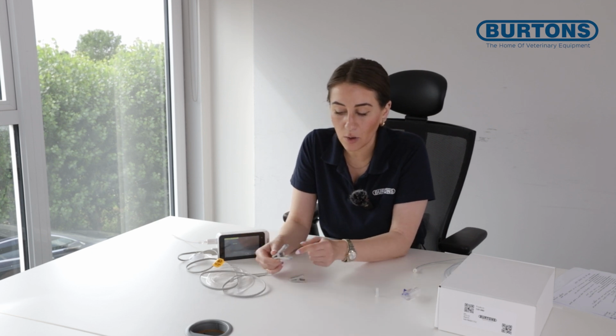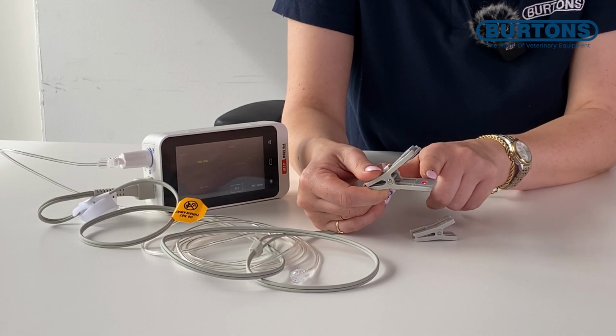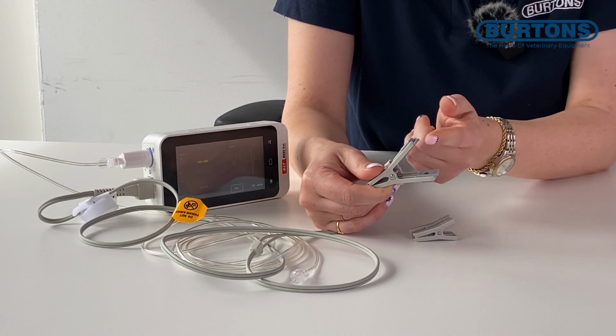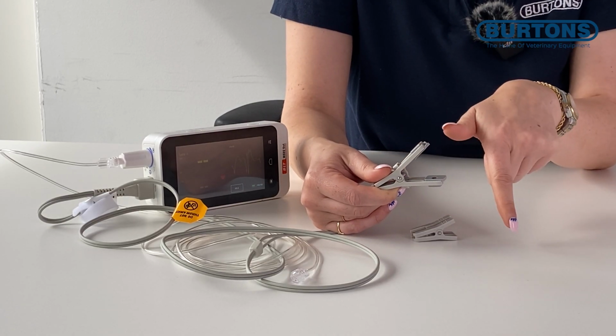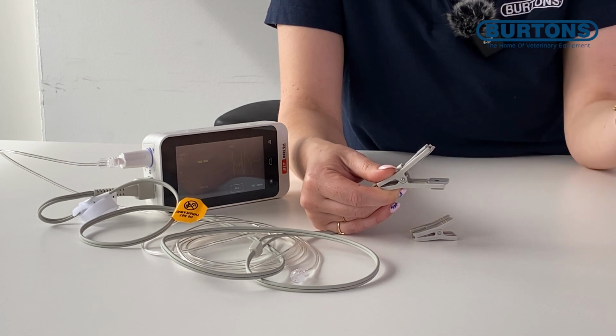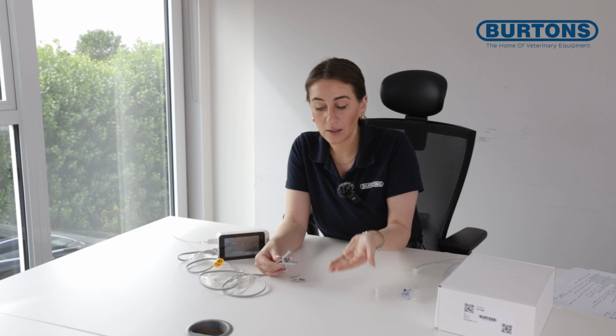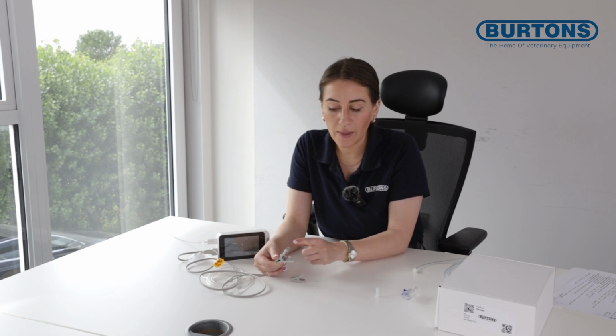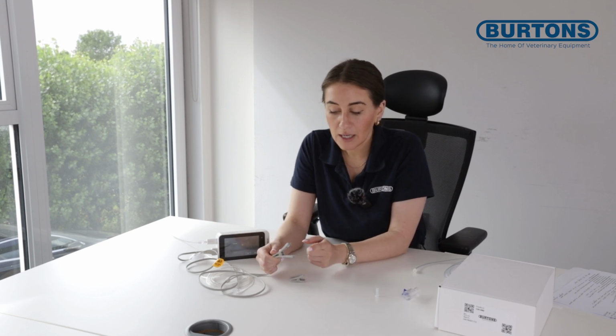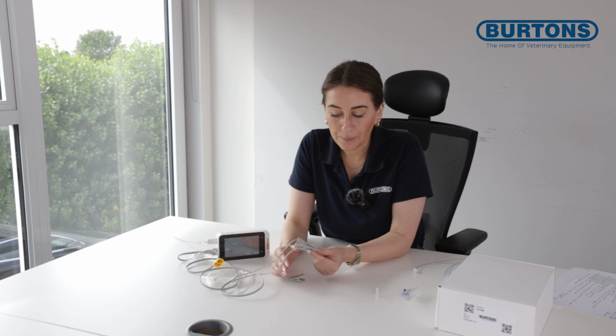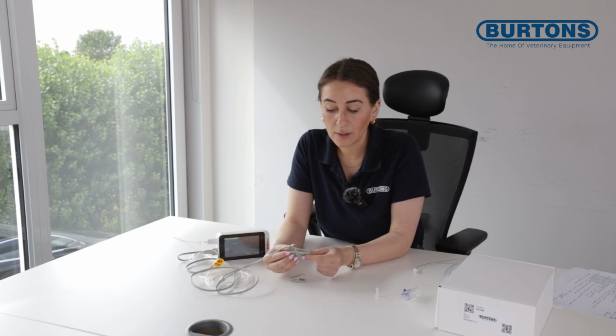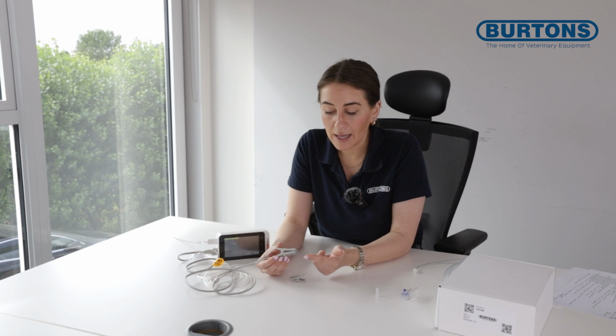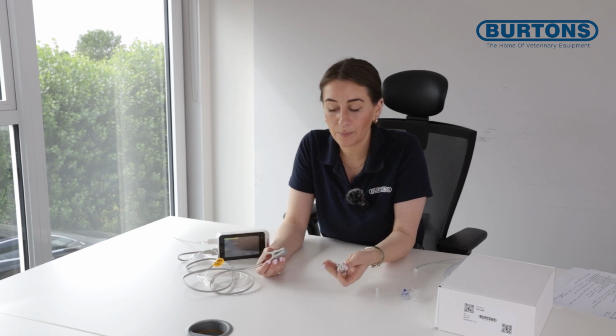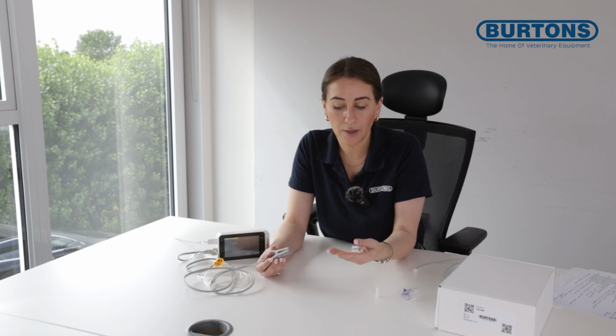And ideally we always have the infrared light coming from below, so we always want our receiver facing downwards, because that receiver can be influenced by other lighting. So if we have it facing to the floor, we're not going to get any lighting impact from above, and that's just to try and improve our contact. So we often get people mentioning that it's difficult to get a reading sometimes on our patients, and when we're using medetomidine, we often have a patient that is peripherally vasoconstricted, and therefore we have less blood to monitor.